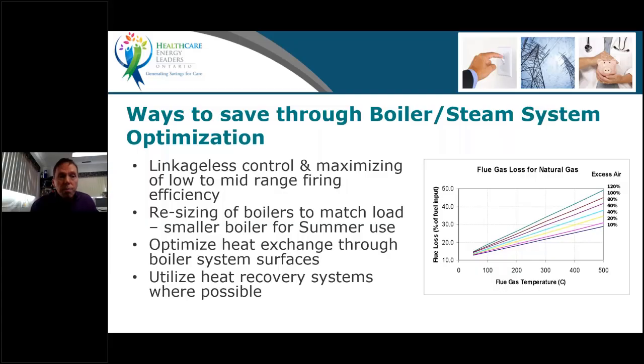At the boiler itself, you want to look at, what is my excess air? Where excess air refers to how much air you put in that burner in order to get proper combustion. If you have too much air, then we call that too much excess air. It does reduce your efficiency, but be careful that you don't just reduce your excess air, because then you're going to run into other types of trouble. In order to properly control that, there are different, sometimes more expensive methods where you can actually dynamically adjust your excess air based on measurements. You don't see that in small boiler plants, but in larger boiler plants, you'll have trim systems that will dynamically adjust your excess air so you always keep it at the proper match, and you can gain, like I said, quite a few percentage points on your efficiency.